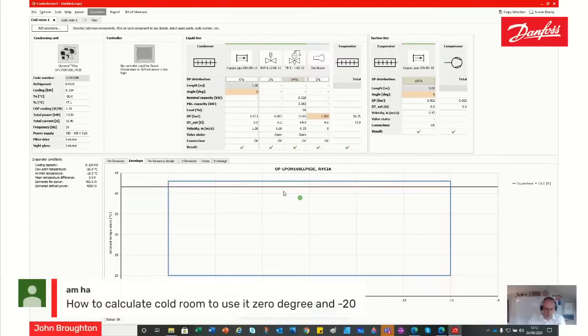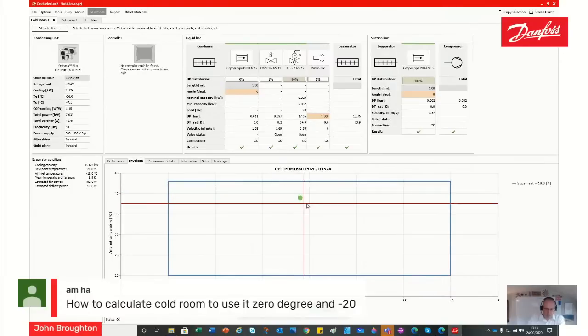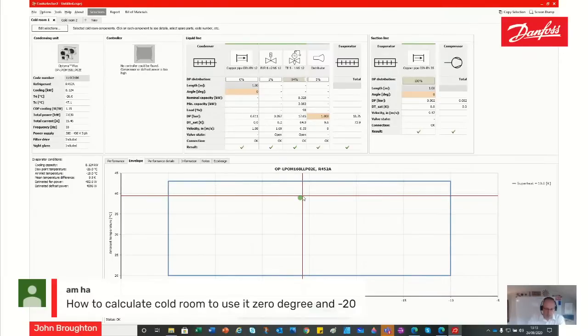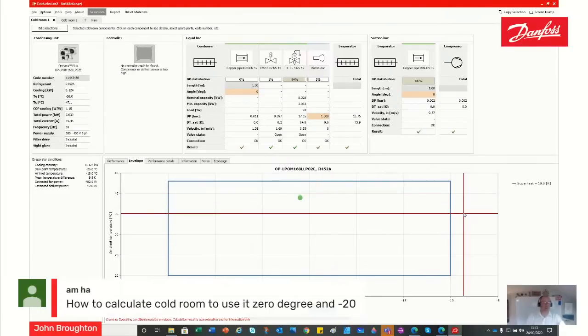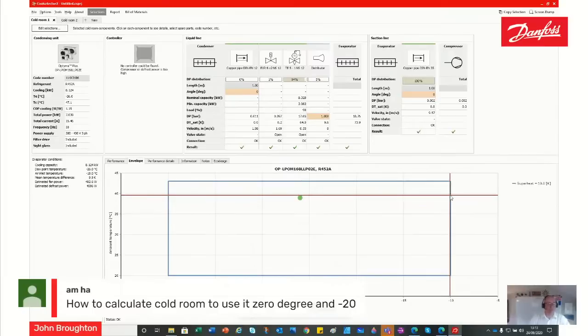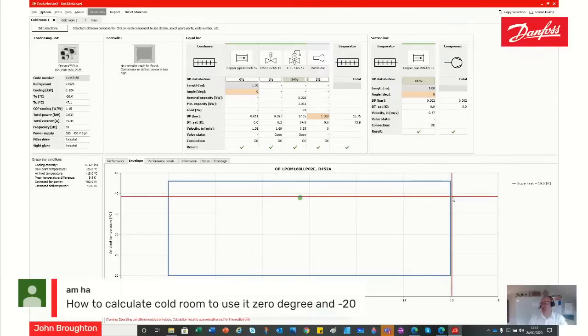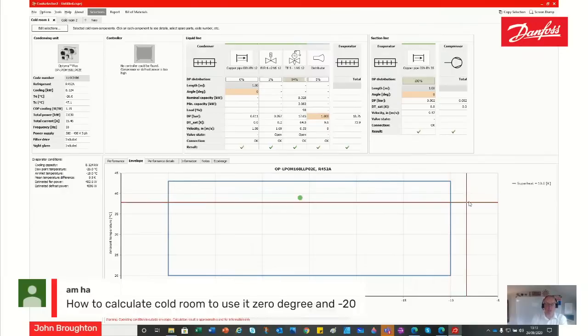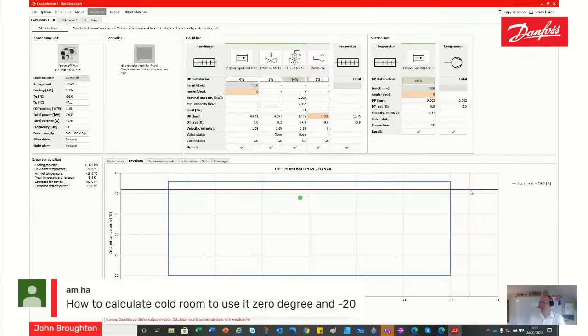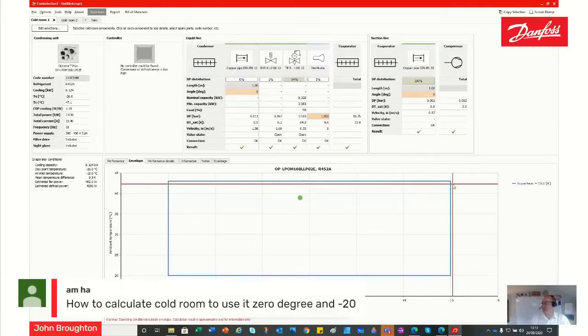The main thing you have to manage and look after is your compressor, and make sure it stays within its operating envelope. If it doesn't, you will kill it quite quickly. Particularly when we're up at high evaporating temperatures like this, the best thing to do would be to fit crankcase pressure regulation on it so that we keep it within its envelope, because if we take it outside of its envelope up here, we'll kill it very quickly. So those are the very basic things to think about. Hope that answers that.